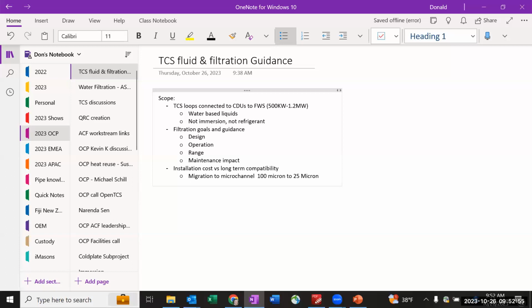But I think what you're saying is, if you started out doing door heat exchangers, and you set your filtration requirement at 100 micron, so you've got conventional cold plates and a conventional rear door cooler. Is it possible then, when someone says 'I want to add microchannel cold plates,' and they swap a server out to something higher power? It'd have to be the whole loop, I would gather.